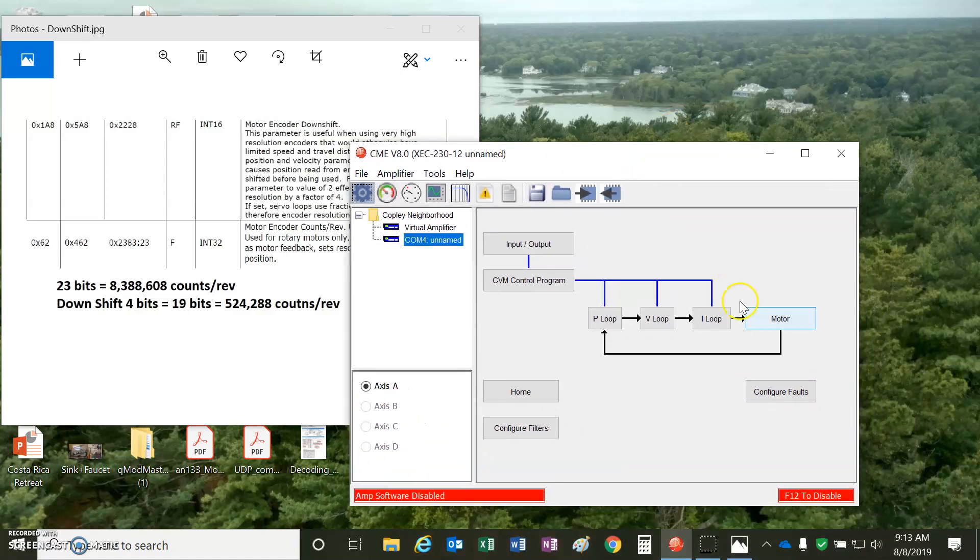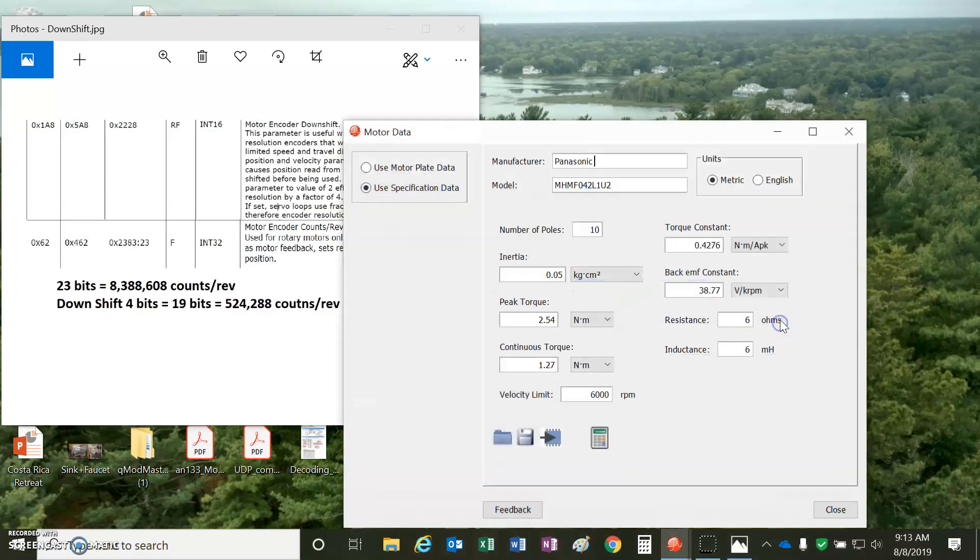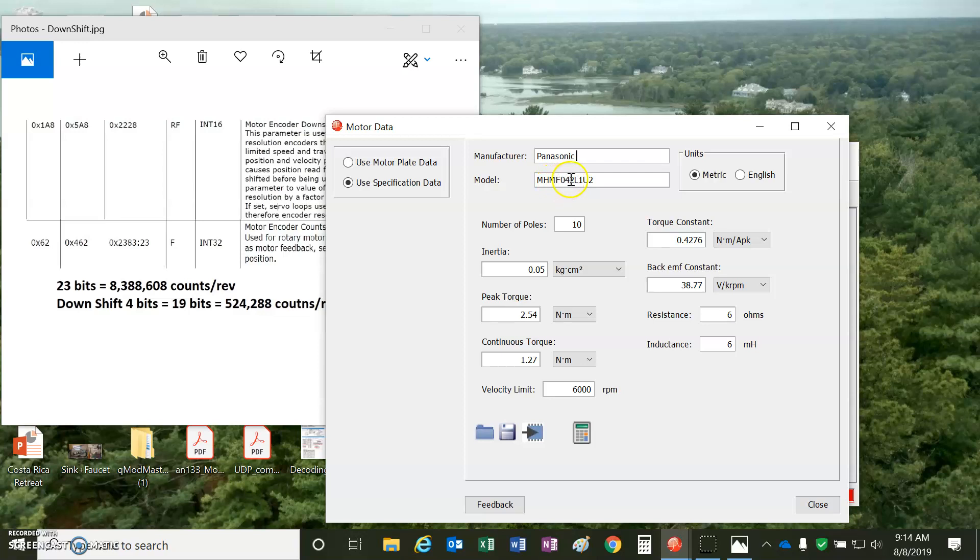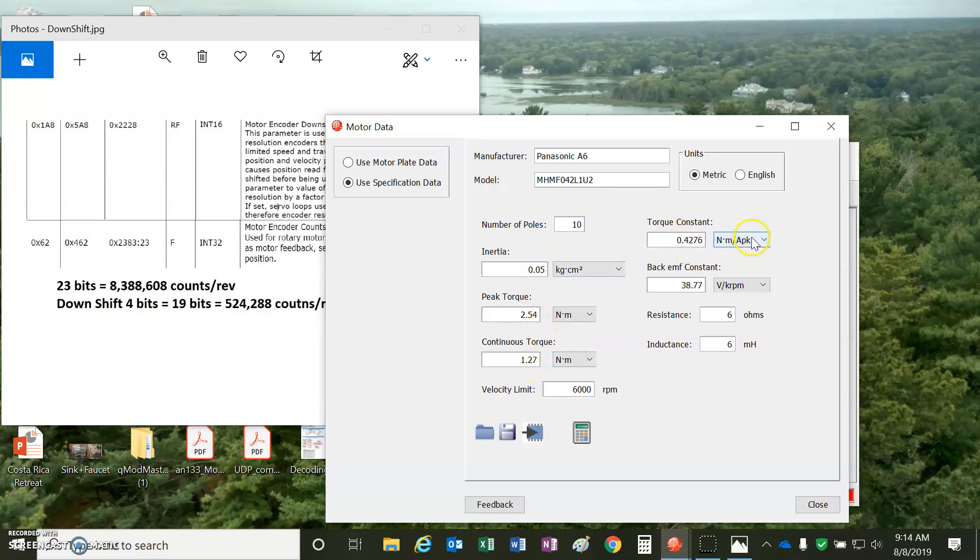Okay, so the basic setup would normally take all the information about the Panasonic. I've got the MHMF 042 motor I'm connected to. That's the larger of these Panasonic A6 motors. They're 10-pole motors. They have a little bit of inertia, some peak and continuous torque, torque constant based on Newton meters divided by amps. I just put that in right from the label there. I just took the Newton meters and divided by the amps.